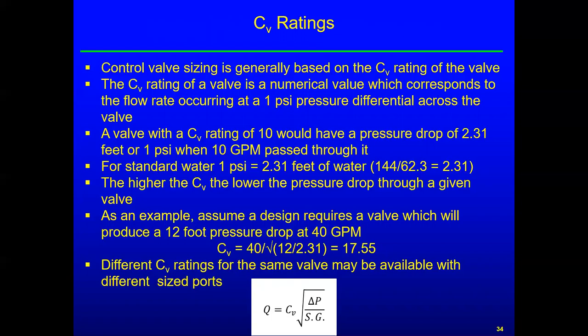And just know 1 psi is 2.31 feet of water, and that comes from 144, square inches per square foot, divided by 62.3. That's the density of standard water. And what is that? That's pounds per cubic foot.